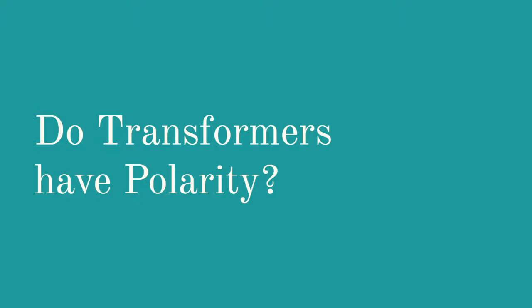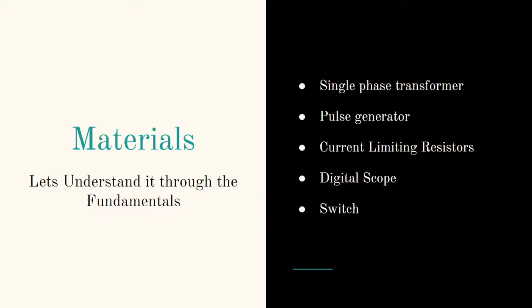You could do an experiment to identify polarity. We'll do a simple experiment to identify the polarity of a transformer and see how it affects the way a three-phase winding can be configured and its vector group. For this we need a single-phase transformer, a pulse generator for the primary power source, current monitoring on primary and secondary, a digital scope to identify voltage and current curves, and a switch to turn the circuit on and off.